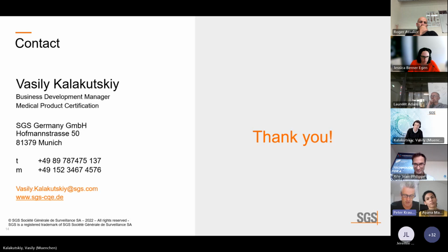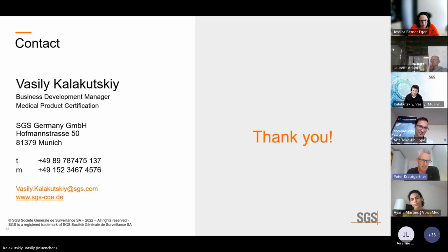Vasily, my question is, you said at SGS routine in terms of ISO and MDR certificates, so quality management and product certificate, you need to apply for the ISO before you apply for the MDR certificate in order to let the audit procedure start.